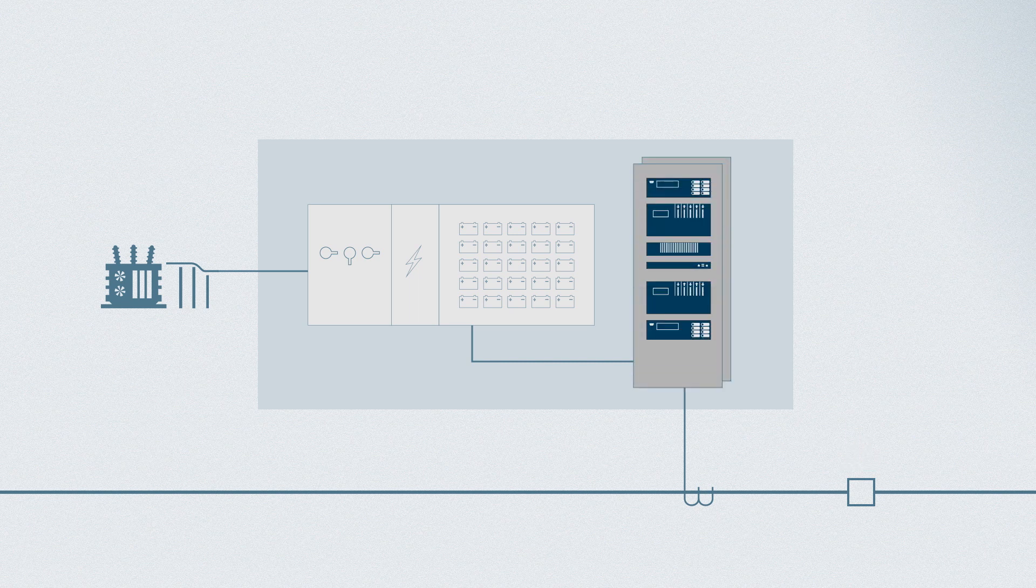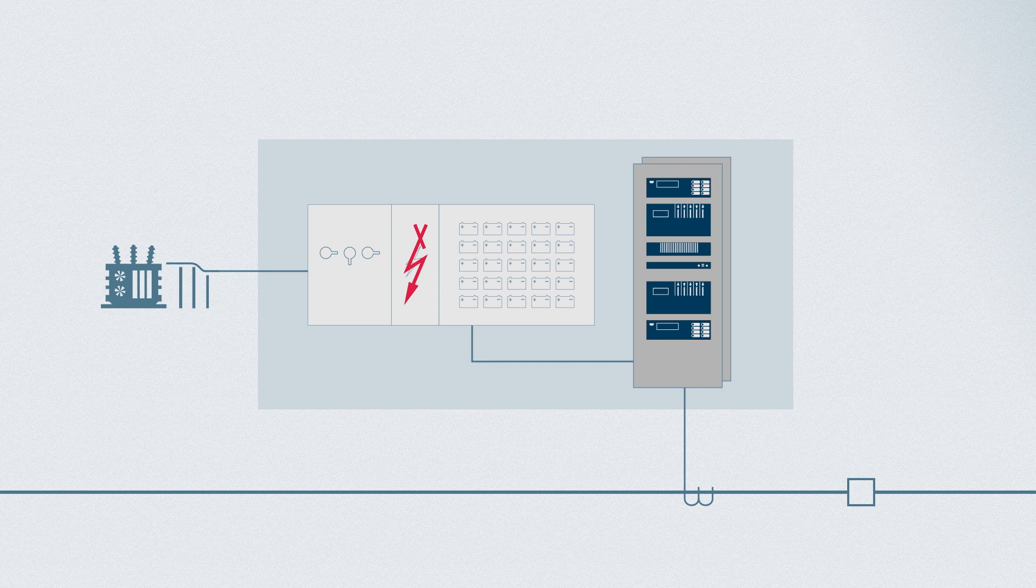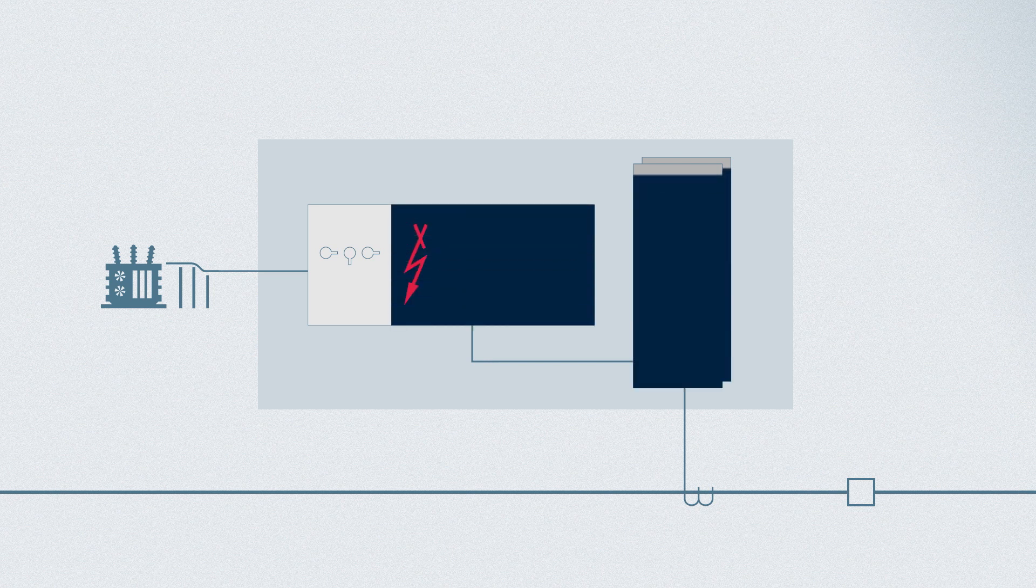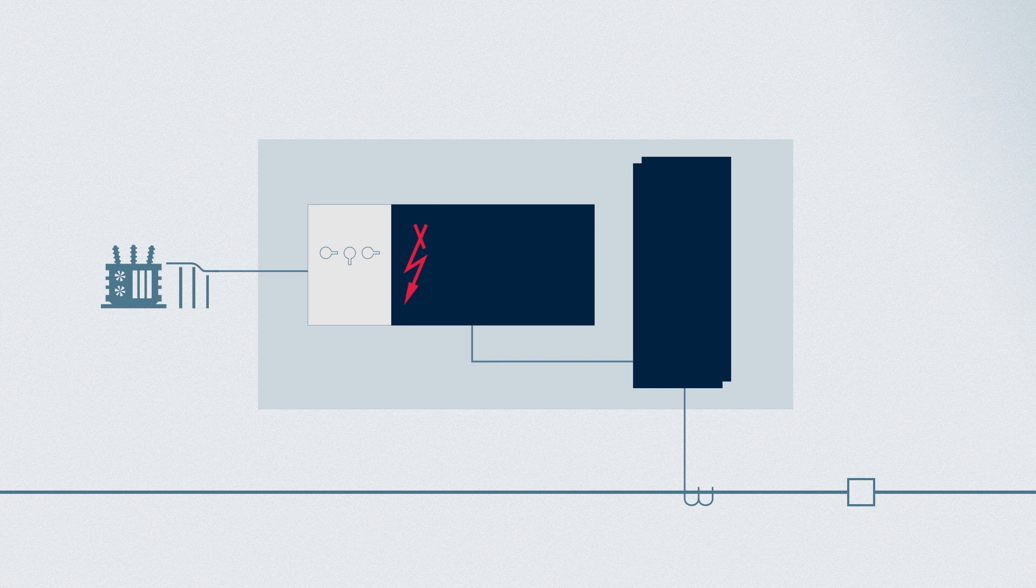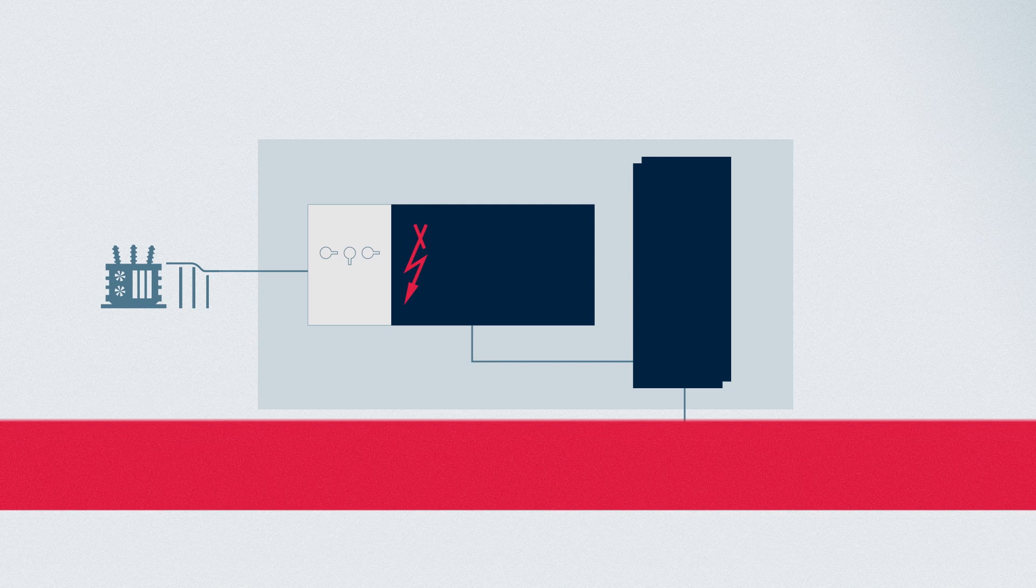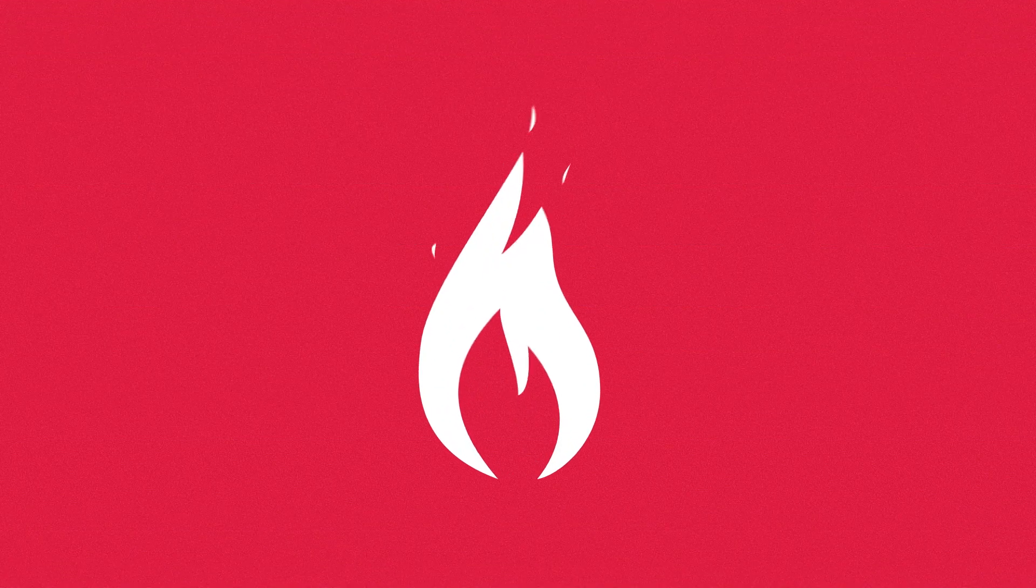But even worse, a fault on the station battery DC system, including unresolved battery charger failures, can lead to a complete loss of power to protection and control equipment, preventing them from detecting faults and tripping breakers. The results of this can be catastrophic.